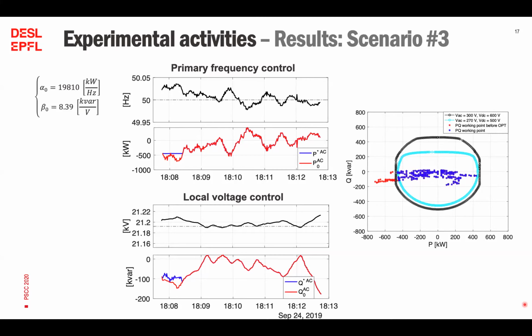On the right, we have a figure that maps the operating points before and after the implementation of the proposed optimal set point calculation. You can notice that thanks to the proposed method, the points falling outside the feasible region have been moved back to the edge of the light blue curve, thus assuring the continuity of the service. So it's important to stress that without this controller, these red dots falling outside the feasible region would have made the converter trip or just provide zero power.